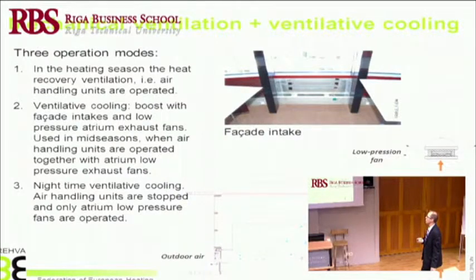So this shows the operation principle of this night ventilative cooling. In the daytime, the system is operated as a conventional mechanical ventilation system with heat recovery, but in summertime you can boost at night the ventilation with a low pressure fan from the atrium, and there are intakes in the facades you can see here, almost in every room.